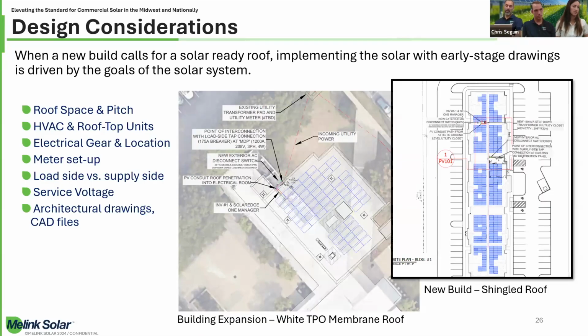Also, the load side versus supply side interconnection. If the main panel of the facility or the main switchgear is large enough and has capacity for us to tie in, we can tie in up to a 20% circuit breaker in that main gear. If we can't do that based on the gear sizing, we can do a supply side connection, which is a little different. It allows us to interconnect the bigger solar array.